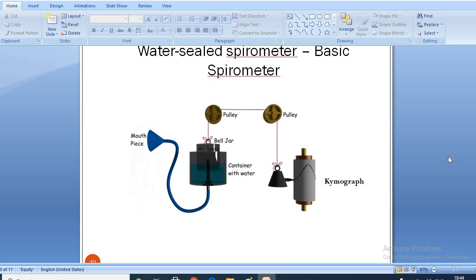When a person breathes into the bell through the breathing pipe, the volume of air trapped inside it gets changed. The changing air volume gets converted into vertical motion of the bell jar and hence the position of hanging weight changes accordingly. This is because another end of the string attached to the bell jar is attached to the weight via pulleys. The patient breathes air into the tube via the mouthpiece. During each cycle of inhalation and exhalation, the jar moves up and down. It depends on the volume of air inhaled and exhaled into or out from the air inside the jar.